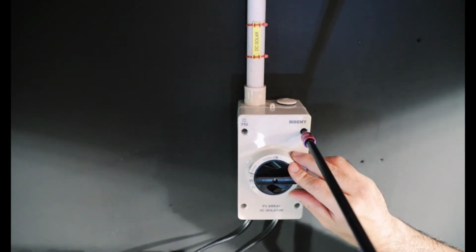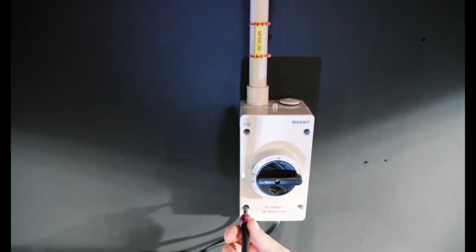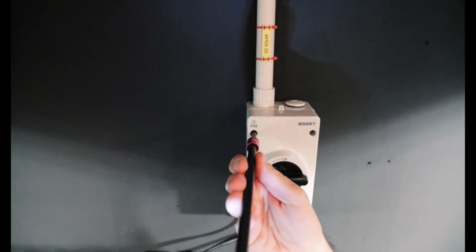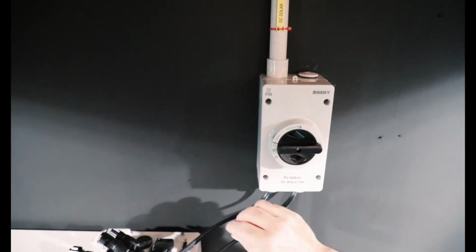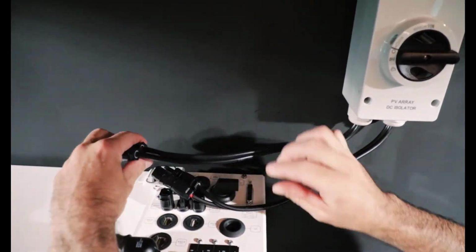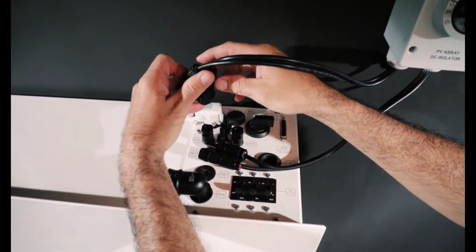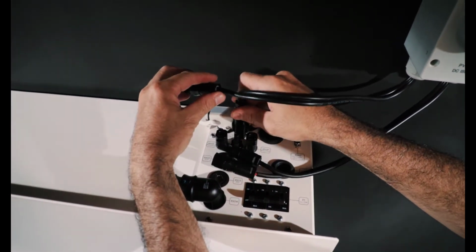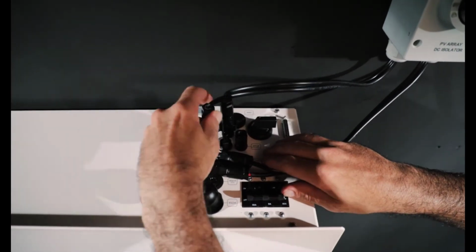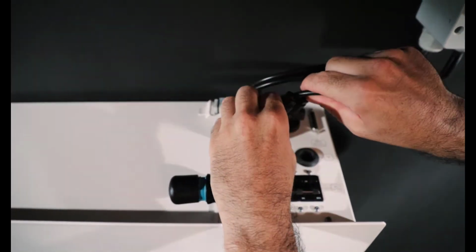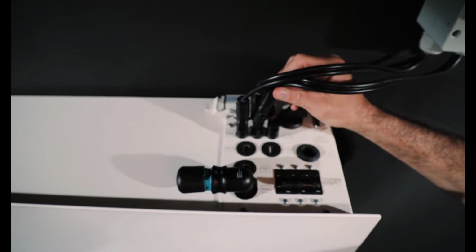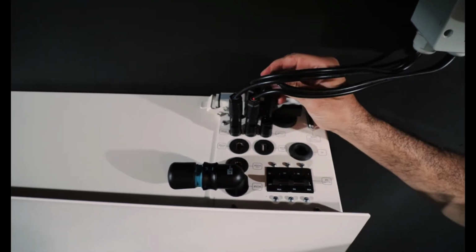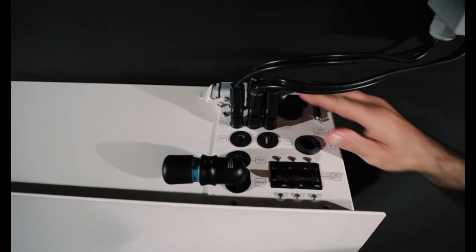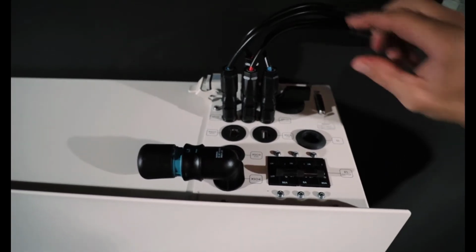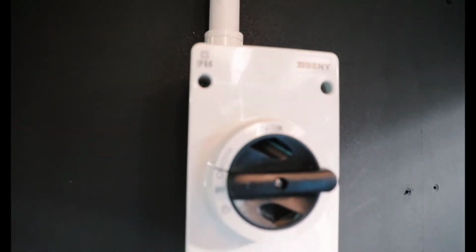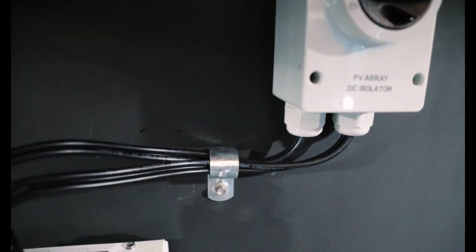Although the hybrid system does have a DC isolator at the top, it's purely there for testing purposes. It's not an applicable isolator under the eyes of the standards. The hybrid system comes with two sets of the Sunclix connectors, so again very straightforward to connect them to the DC. I'm not going to show you how to do that because it's pretty self-explanatory. You don't need any kind of tool or anything, and you've got the dual MPPTs. So if you don't use both MPPTs, the system does come with blanking plugs, so you can blank those off.